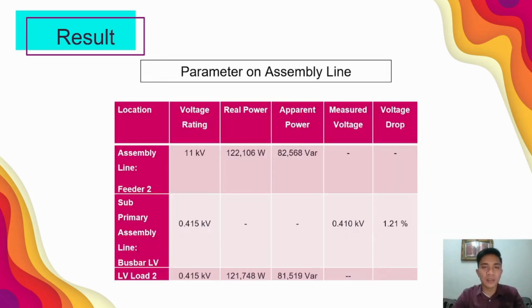Okay, continuing to the parameters on the assembly line, which is recorded at feeder 2, SPDB line, busbar and LV load 2. The voltage rating is stepped down from 11 kV to 0.415 kV by using a step down transformer. So the real power measured at feeder 2 is 122,106 watt, which is higher than the LV load, 121,748 watt. While for the apparent power, LV load 2 and feeder 2 obtained 82,568 var and 81,519 var respectively. Hence, the measured voltage at the LV busbar obtained 0.410 kV along with 1.21% voltage drop percentage.